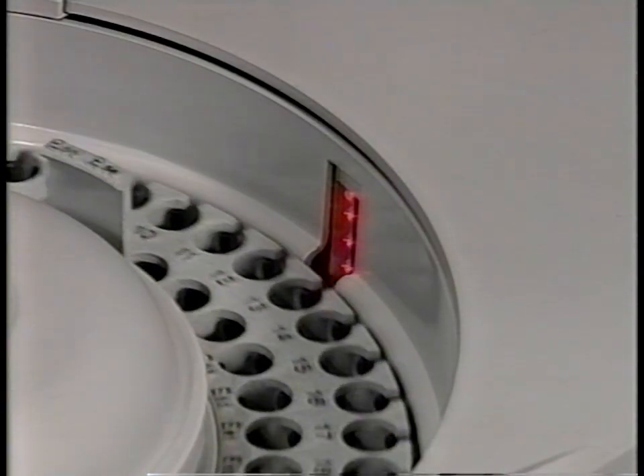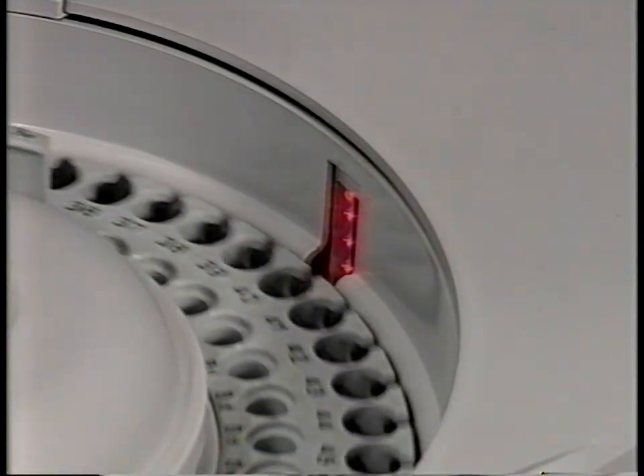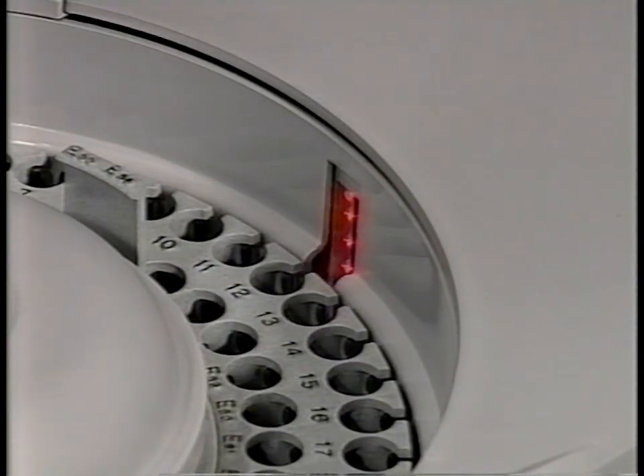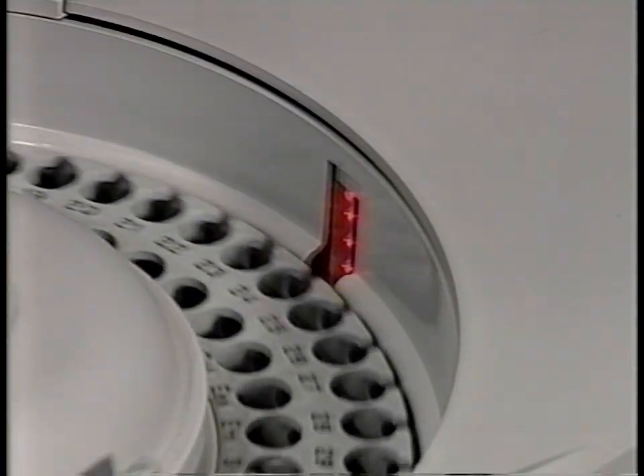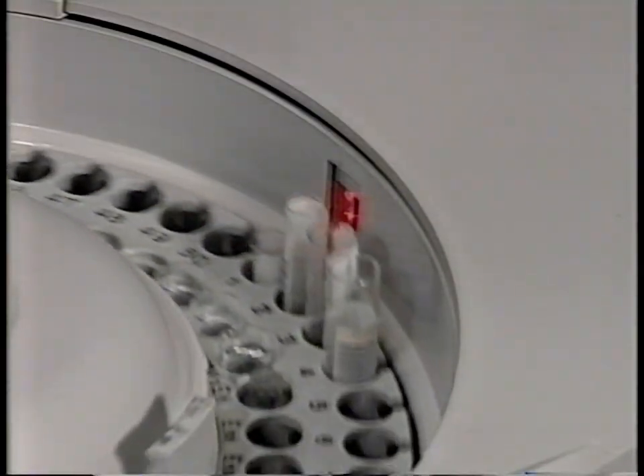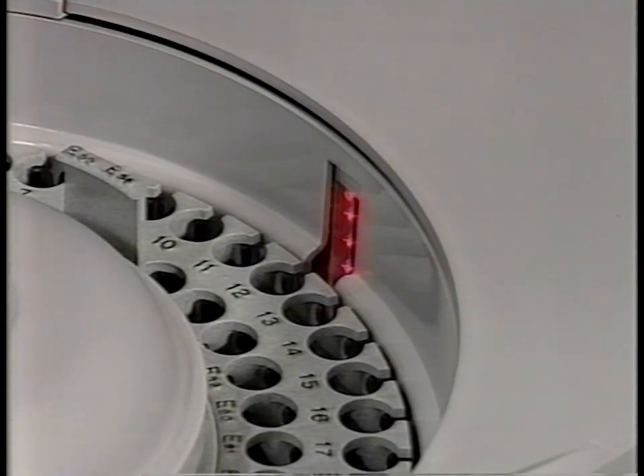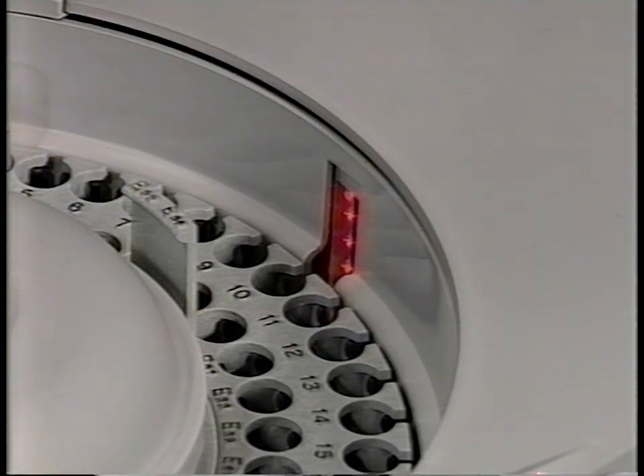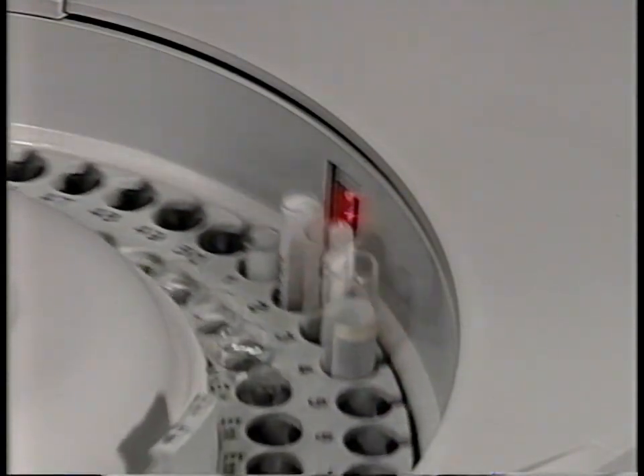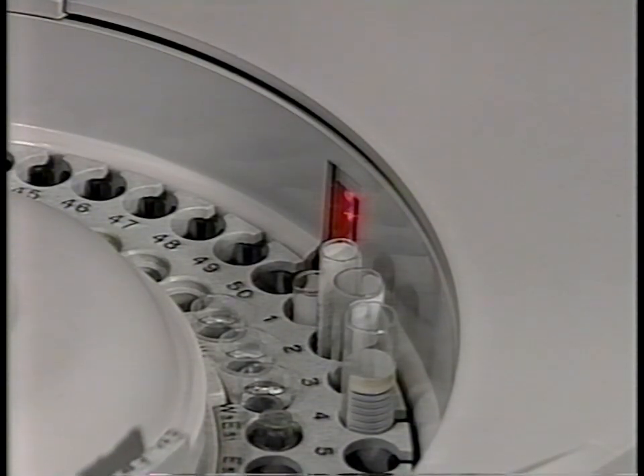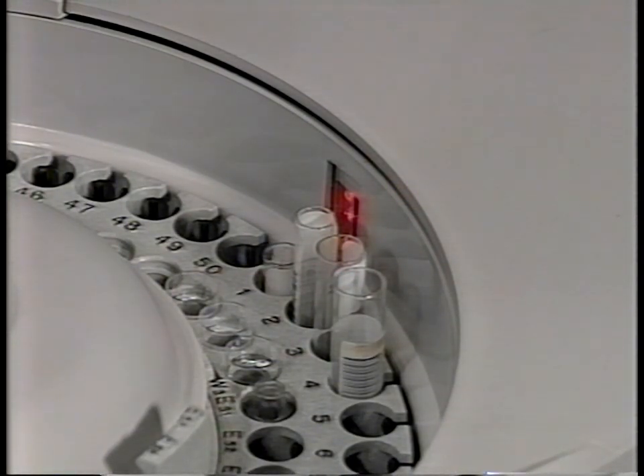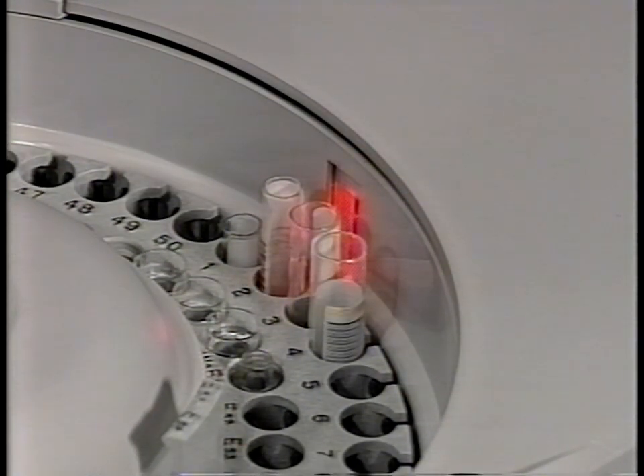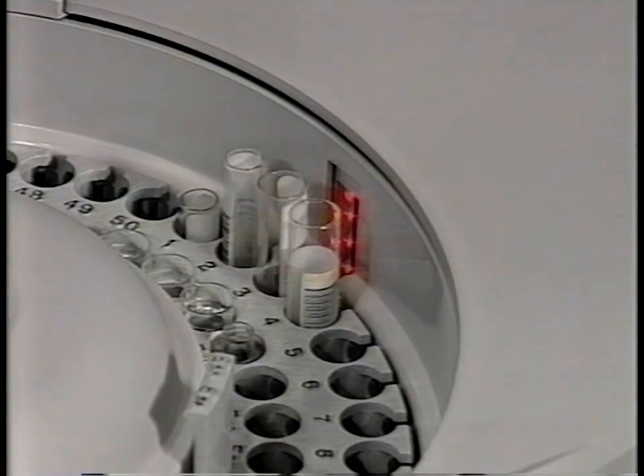The sample disk can hold different types of sample cups and tubes without the use of special adapters. There are 50 positions on the outer ring for routine sample placement. Samples can be added or removed as needed by the operator. The analyzer can be run with or without the use of its sample barcode reader. The barcode reader is auto-discriminating, and it recognizes 4 types of barcodes.